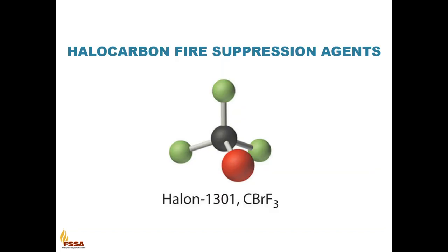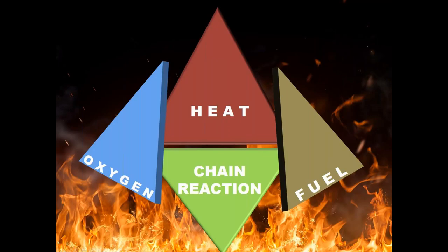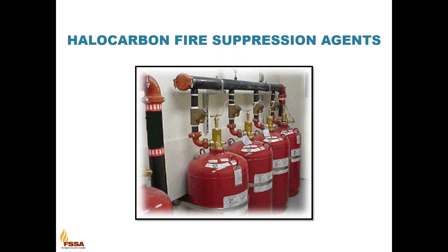The first group that we'll cover is the halocarbon fire suppression agents. These are the agents closest in design and performance to halon. They are primarily HFCs and fluoroketones that extinguish fire at the molecular level, not by displacing oxygen. They function primarily by removing heat, but they also contribute to the interruption of the chain reaction that is combustion. These agents are stored as liquids and are rapidly converted to a gaseous state upon discharge.